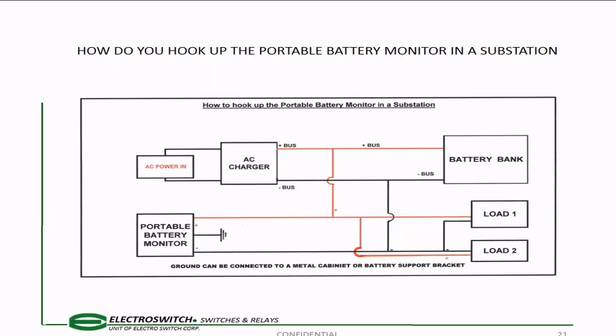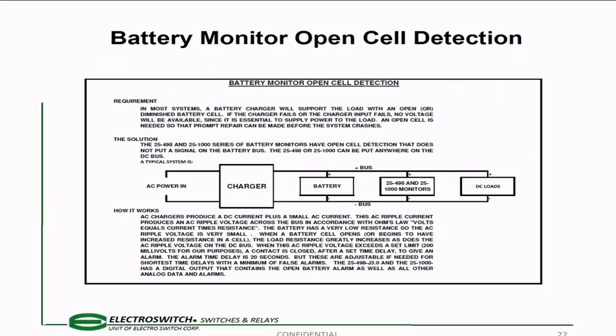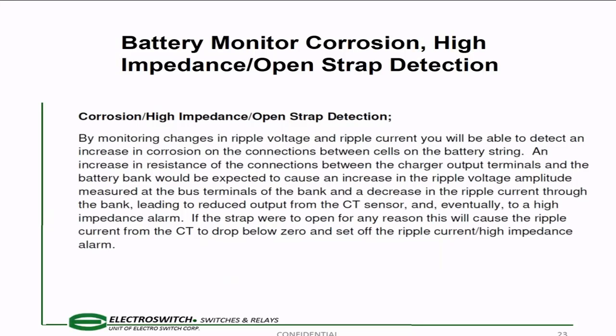And then the only other thing we have to do, if you're going to be monitoring the impedance, I'll get to that in a second. This is just an explanation of how the open cell detector works based on impedance monitoring. If you're monitoring your impedance, your ripple voltage goes above 200 millivolts and your current goes to 0, you have an open cell. So it basically explains that for you. And this is impedance monitoring associated with loose strap corrosion taking place at the terminals.